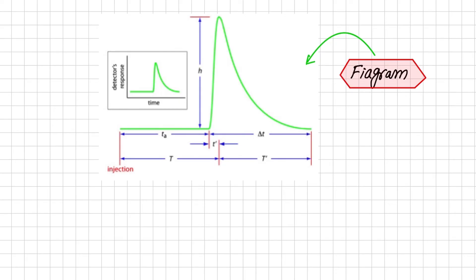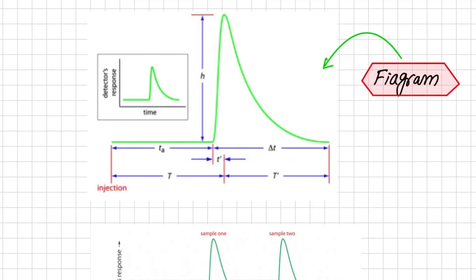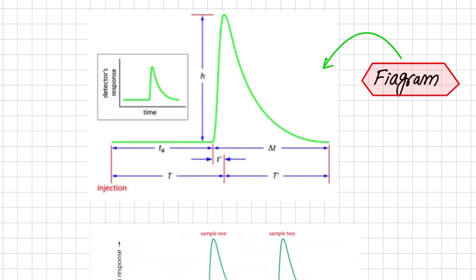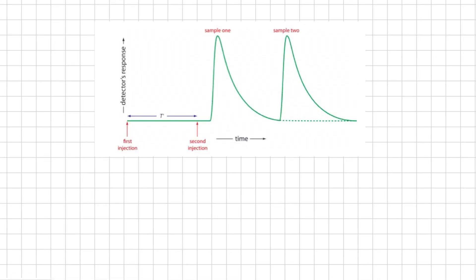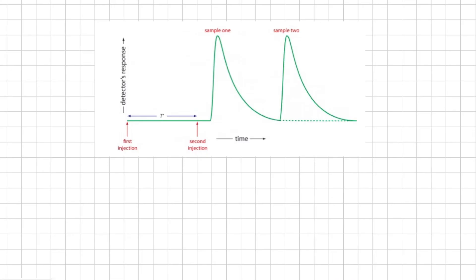The final characteristic parameter of the FIAgram is the sample's peak height, represented by H. Of the six parameters described, the most important are peak height and return time. Peak height is important because it is directly or indirectly related to the analyte concentration, and the sensitivity of an FIA method is determined by the peak height. Return time is important because it determines the frequency with which we inject samples. If we inject a second sample at time T′ after injecting the first sample, there is little overlap of the two FIA curves, giving us the maximum possible sampling rate.